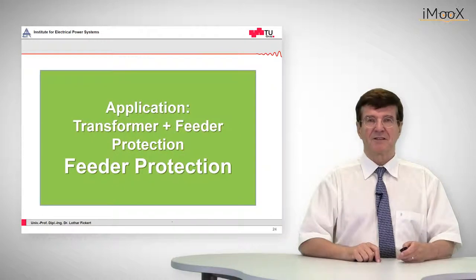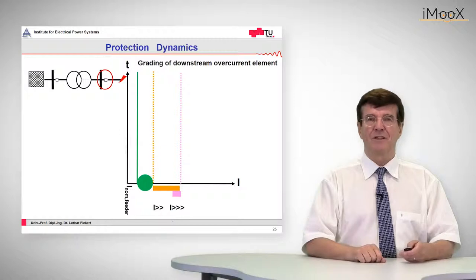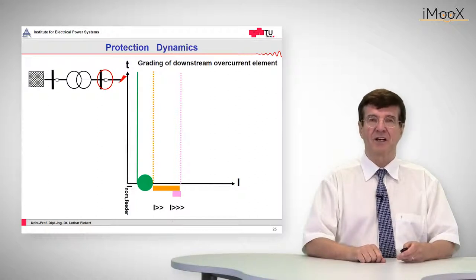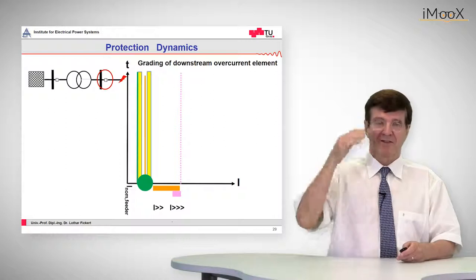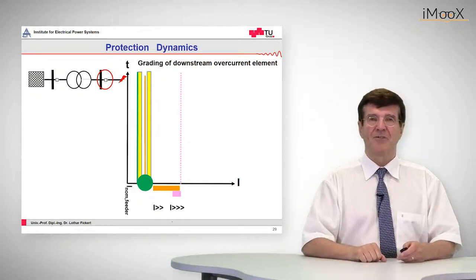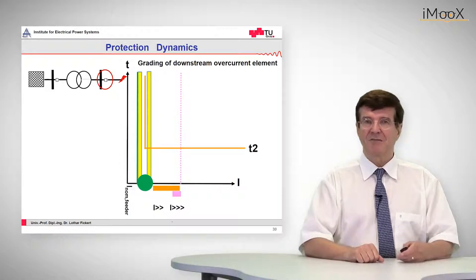The next element is the feeder protection. In overcurrent time grading, we must work our way from the end towards the source. We have two limits: one is the nominal current of the feeder, and the other is the worst case lowest short circuit current, which is a short circuit at the far end of the longest feeder. We can choose a pickup value here, but again we must not infringe with the safety margins. It must always pick up for the worst case, so it must be below that short circuit current, and it must not infringe with normal operation, so it must be above the nominal current of the feeder. The tripping time is chosen as T2.